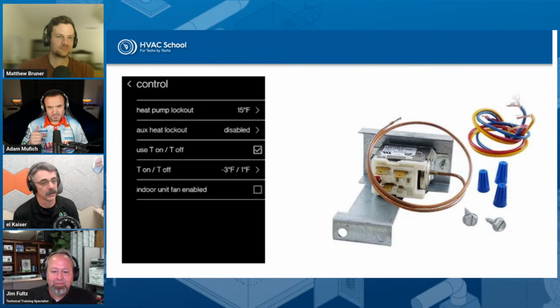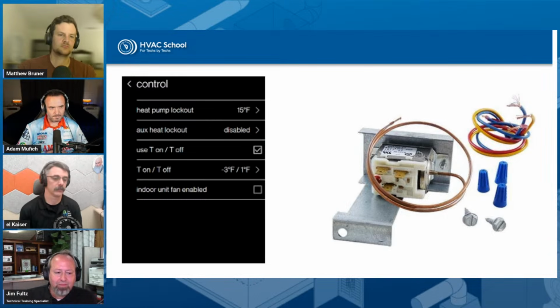The one that you have on the screen, it's a Daikin thermostat, right? And if you look at T on, T off, that's actually the control set point for when the auxiliary heat is going to cycle. So T on, the thermostat has to droop 3 degrees under set point for the auxiliary heat to come on, and T off means you have to surpass the set point by 1 degree Fahrenheit in order for the auxiliary cycle to end. But you could customize. I think almost every thermostat will give you some kind of customizable droop. Yeah.